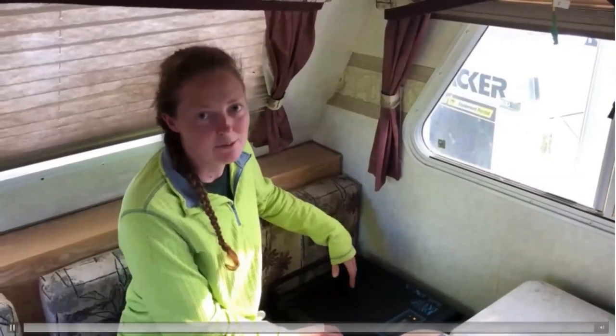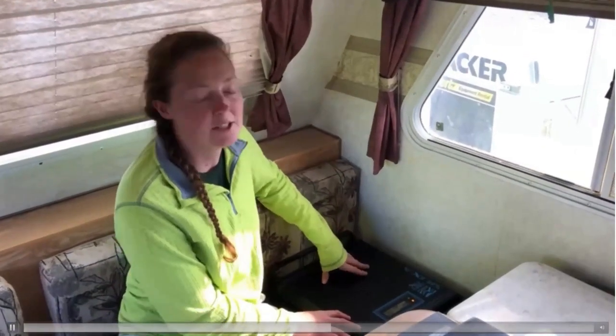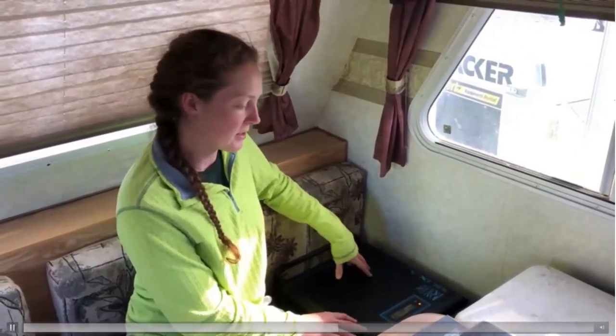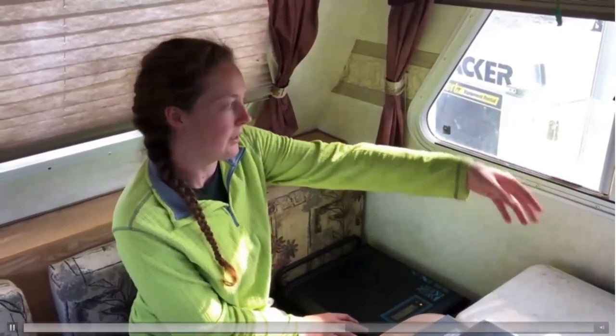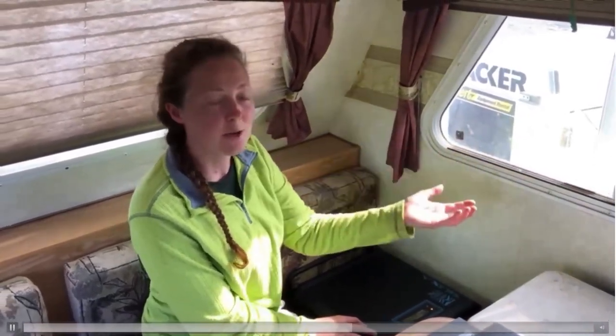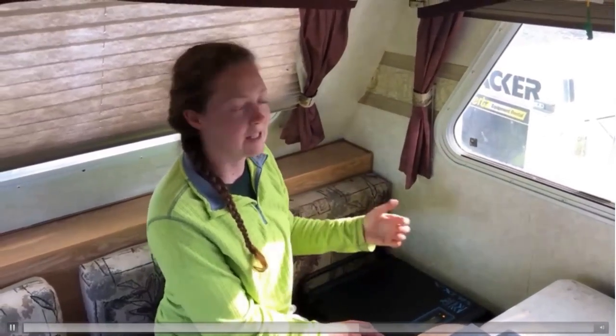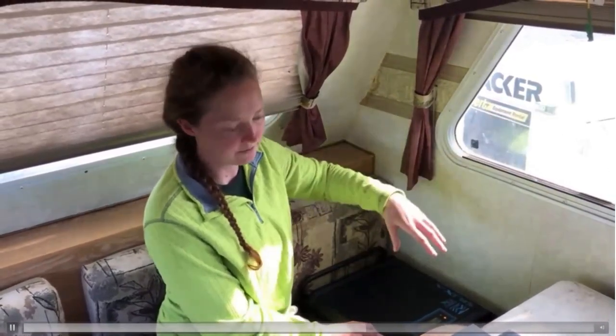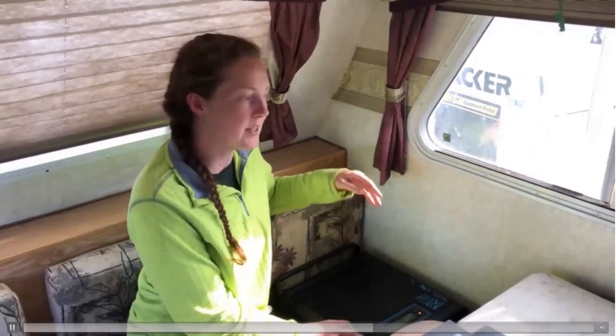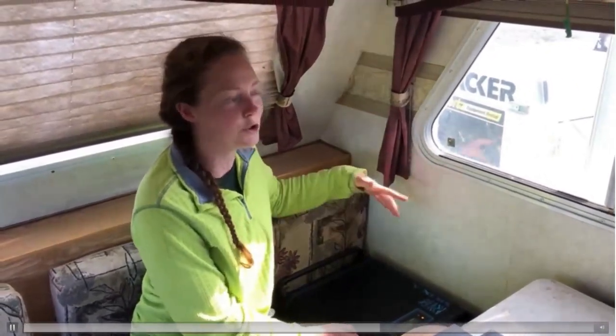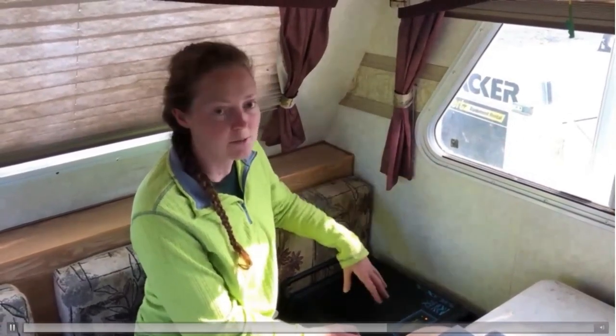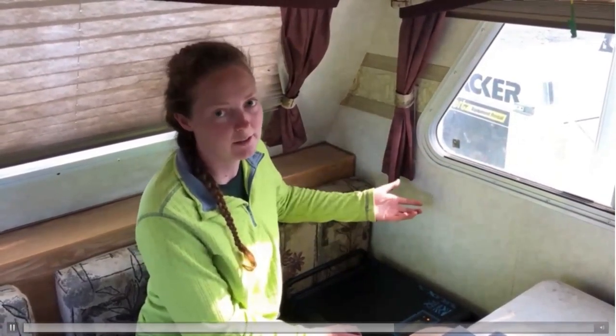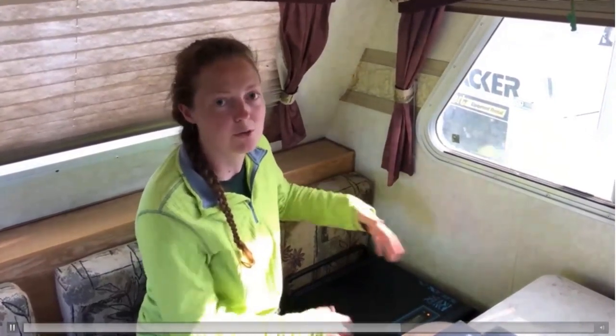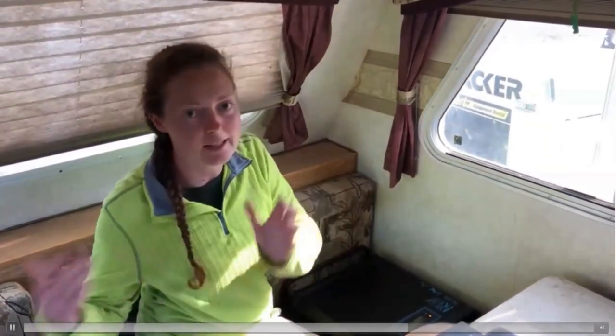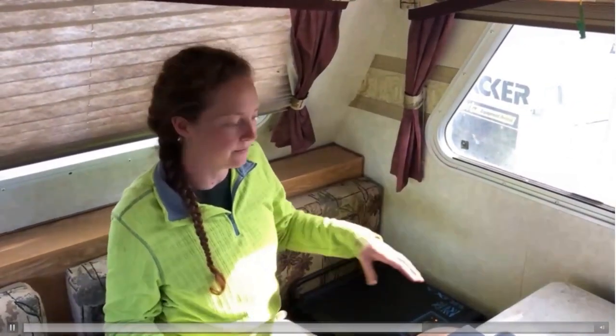Down here, we have the fiber optic component. So this black box is a digital temperature sensor, and it sends a laser down the blue fiber optic cable and into the well. And the response is what allows us to measure temperature at 25 centimeter intervals throughout the whole fiber cable. This measurement is taken at each of these points every 3 minutes for the whole duration of the test. That means it starts before we start injecting heat for our initial profile. It continues to record temperature for the 2 days of heat injection, and then it keeps going for the last 4 to 5 days, measuring the recovery as the ground comes back to equilibrium.